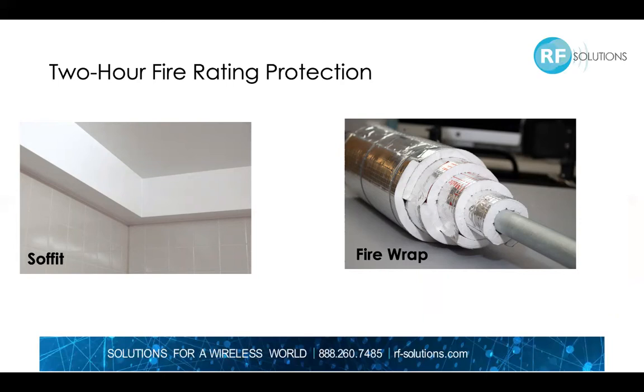Soffits typically take up a lot of space, anywhere from 6 to 12 inches, and require 12 inches of clearance. Fire wrap requires conduit, takes up to 8 inches of space, and has an 8-inch bend radius. The project constraints and budget will determine which protection is optimal.